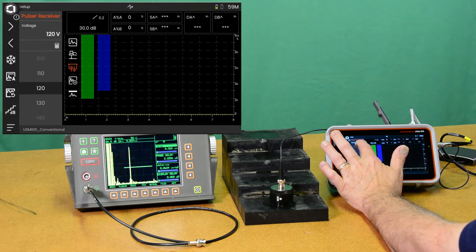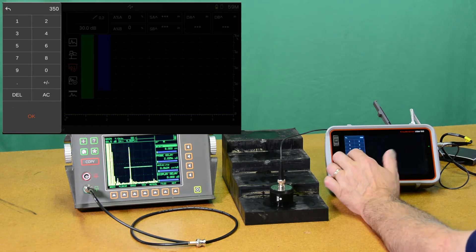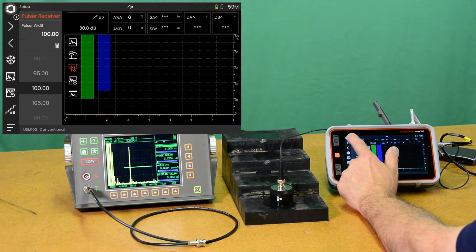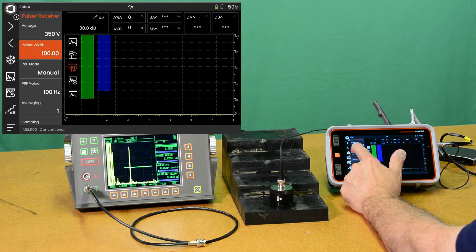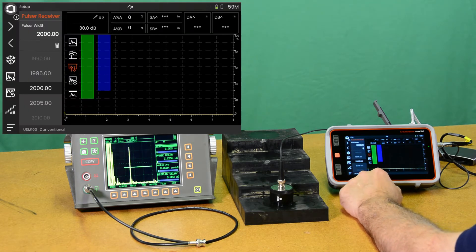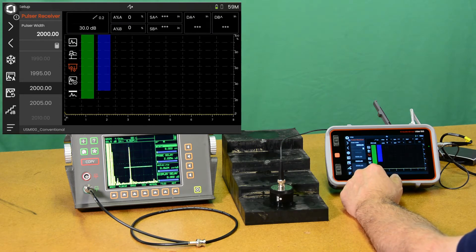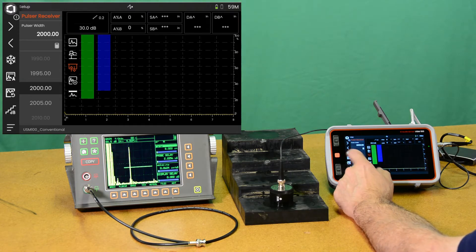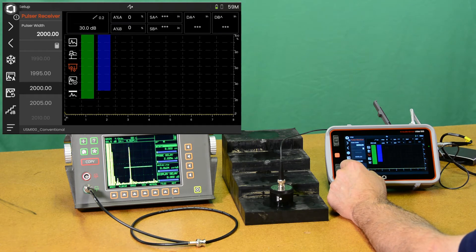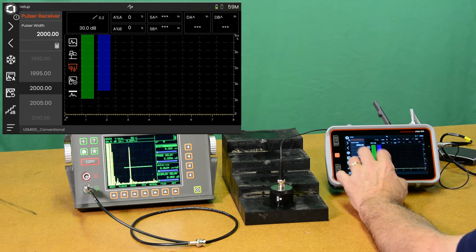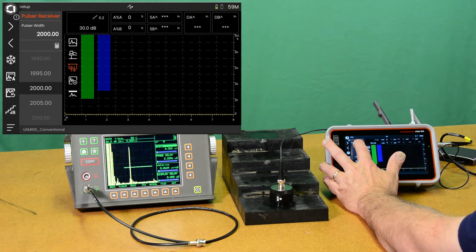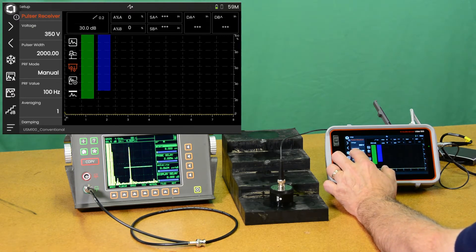We're going to max out our pulser at 350 volts. And we're going to take our pulse width to 2000 nanoseconds. So the 500 kilohertz pulser, one complete cycle of the ceramic is going to be 2000 nanoseconds, one over 500 kilohertz. Ordinarily, half wave, so about half of that would do well. But I found with this pulser, all the energy we can give this probe is the best performance that we get out of it. So we're going to call that 2000.